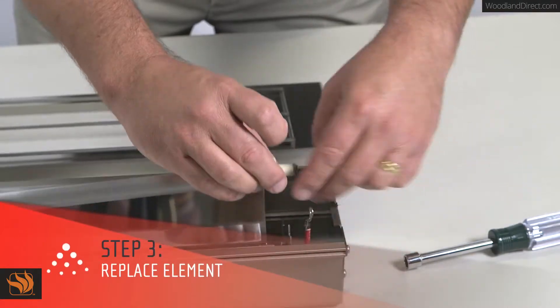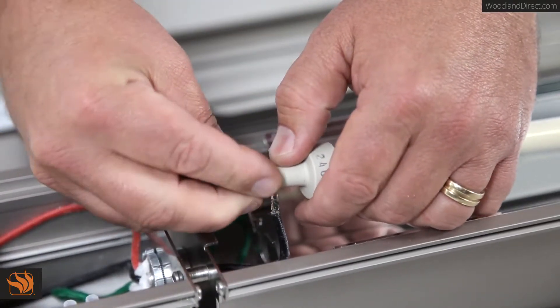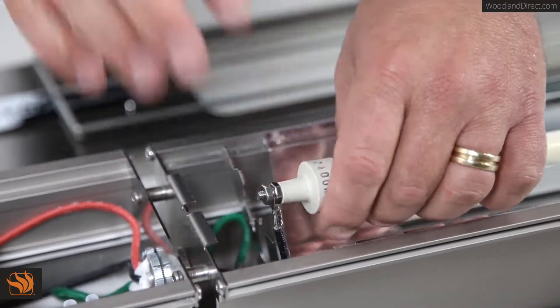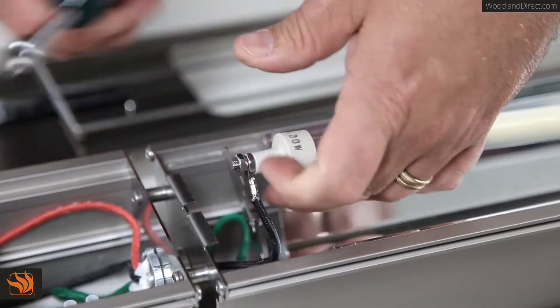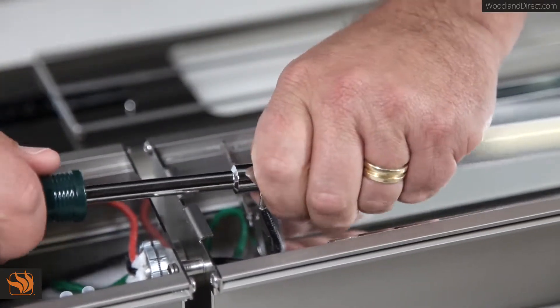Now it's time to replace the old heating element with the new heating element. Once the element is in place, reattach the ring terminal to the element and start rotating the outer nut with your fingers. Be sure to hold the ceramic cap with your thumb near the ring terminal so it doesn't rotate. Next, tighten the nut with the 11/32-inch nut driver. Repeat this step on the opposite side.